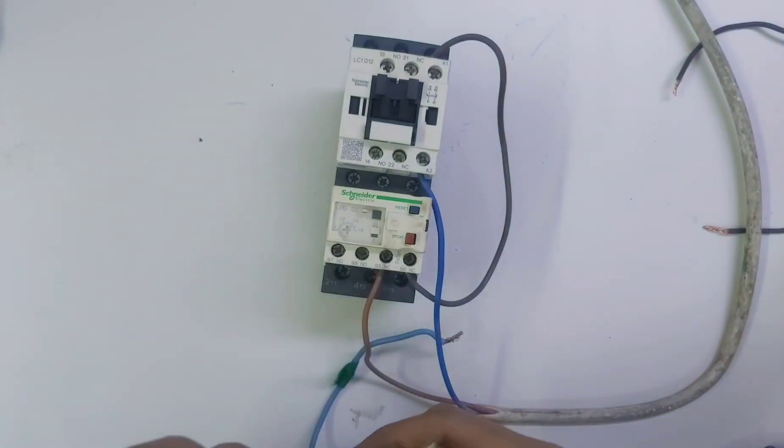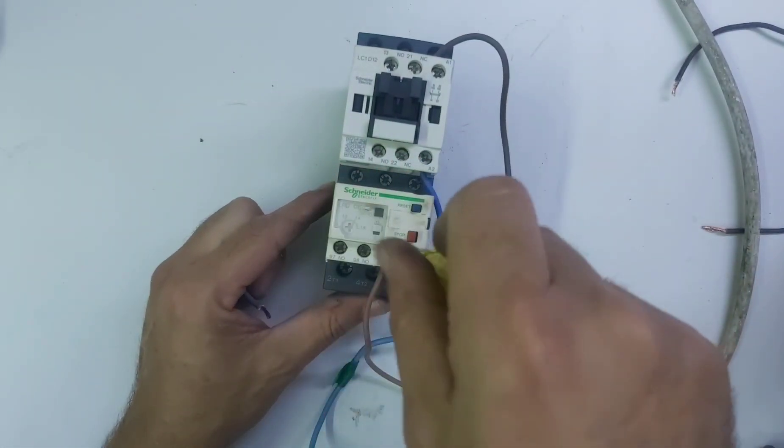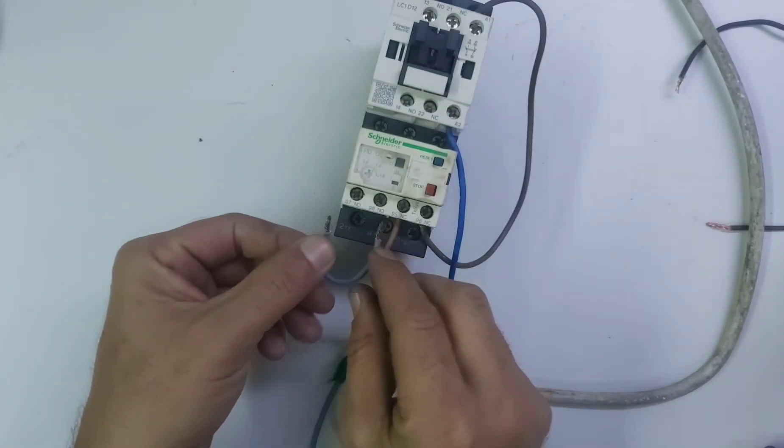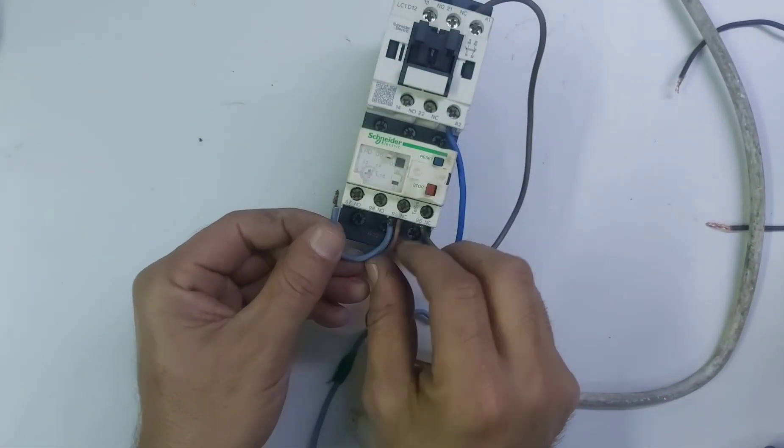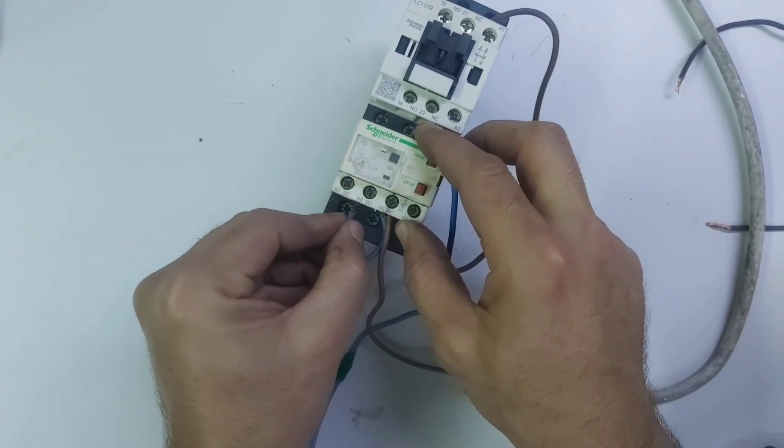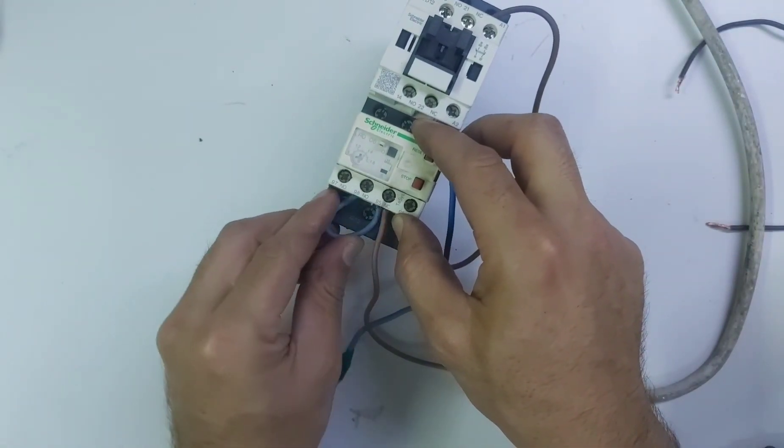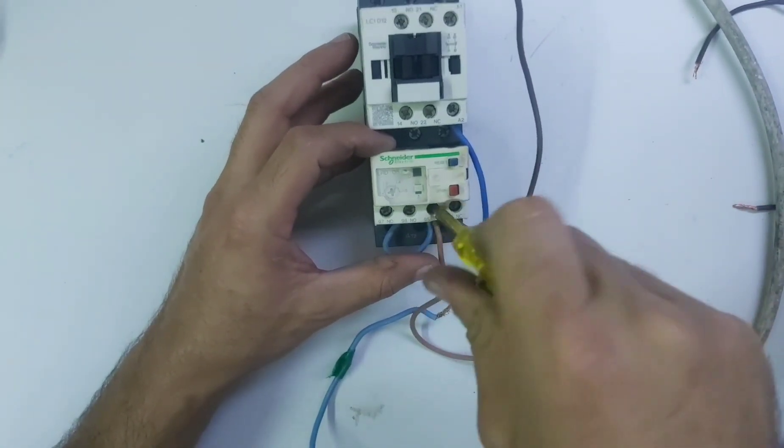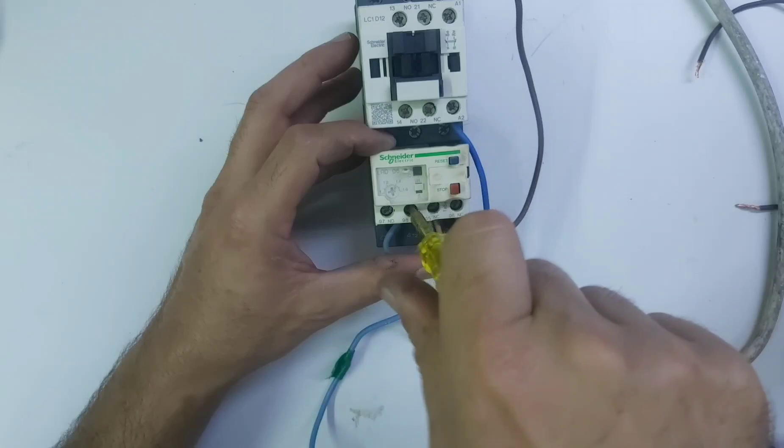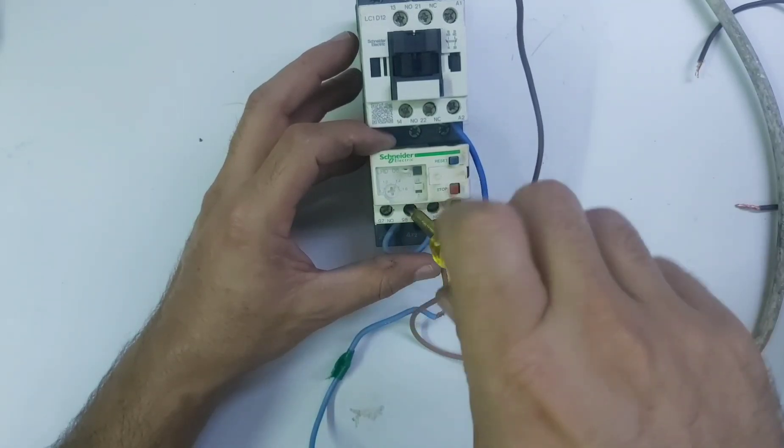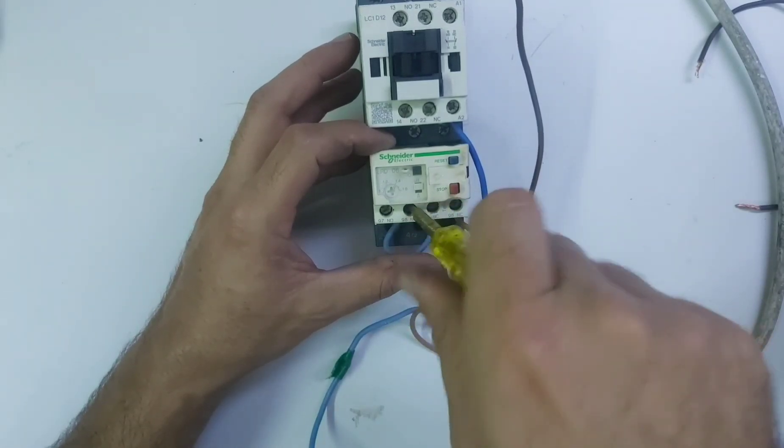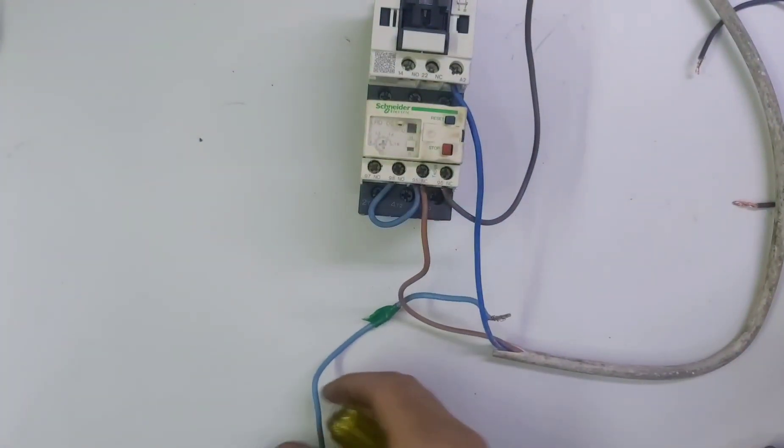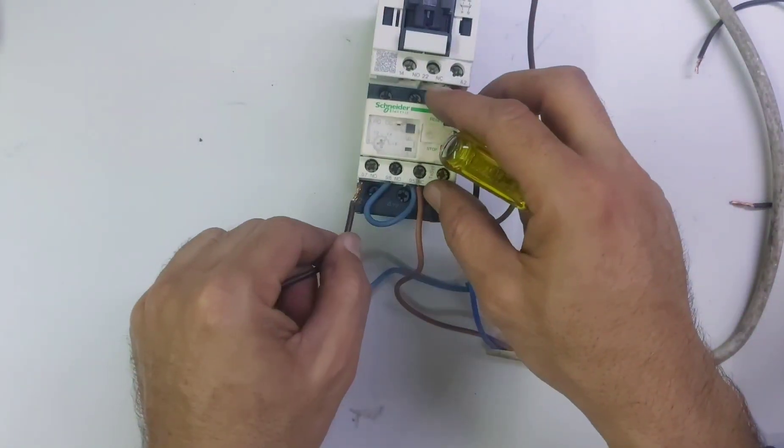And here you need to loop for the trip indicator. This loop will connect here, this loop will connect here from 95 to 98. And you need to connect trip indicator, so trip indicator you need to connect number 97.